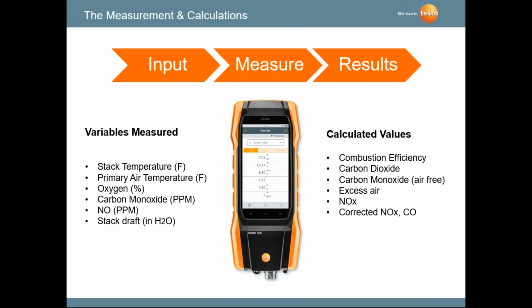So when we look at combustion analyzers, we've got to look at it for the commercial side. For Testo, it's a Model 300 combustion analyzer. You see the 300 here. It has the capability of measuring stack temperature through a probe and hose assembly using a thermocouple. We have a primary air temperature at the bottom. We specifically look at oxygen in the flue gases, carbon monoxide (CO) in the flue gases, NO in the flue gases. And we also look at pressure, negative and positive pressure, stack draft in the flue gases.